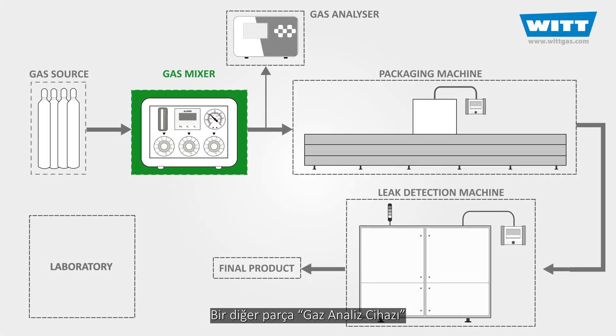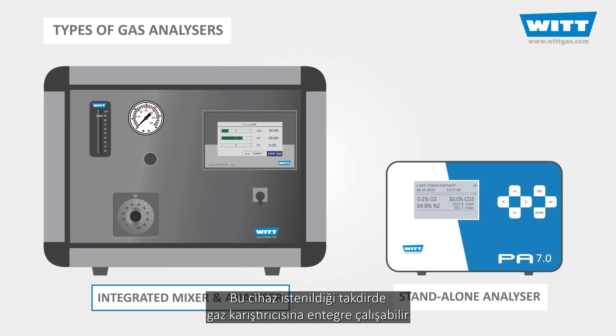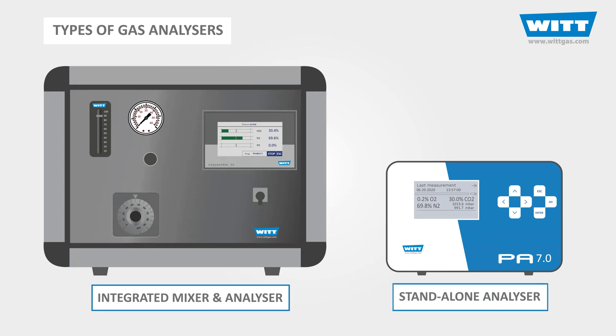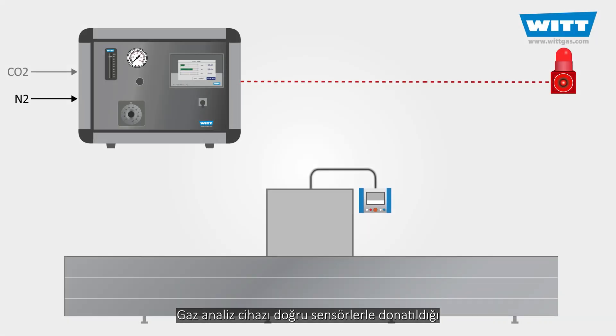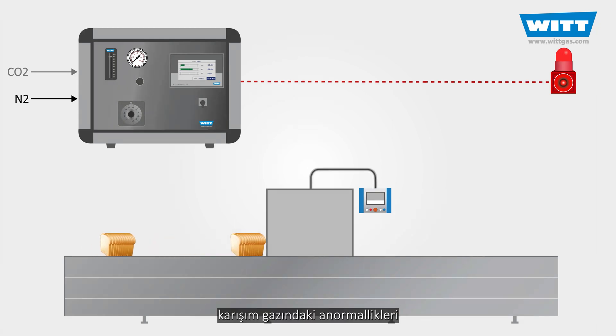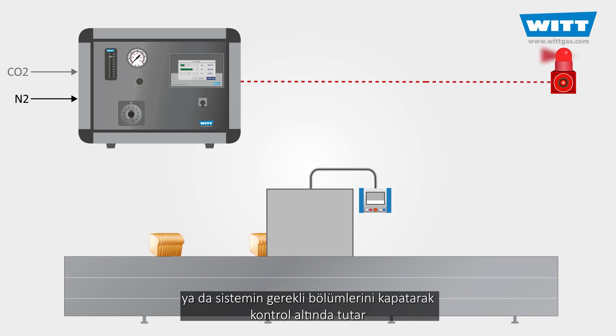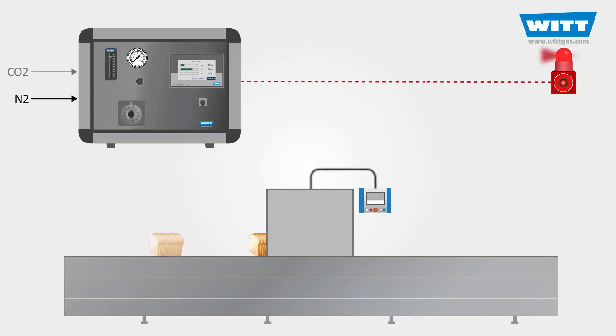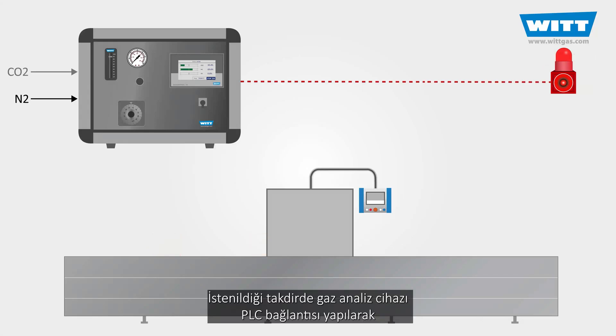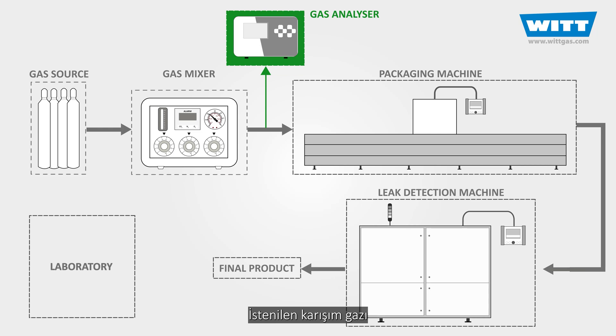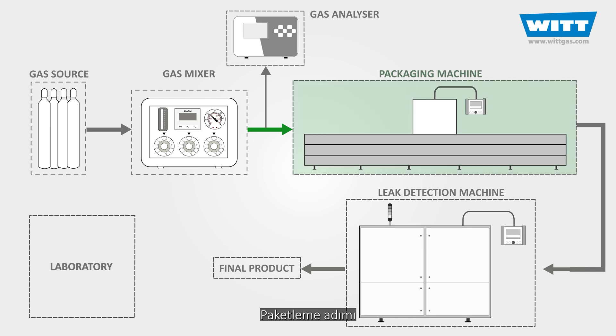The next component is the gas analyzer, which could be integrated into the gas mixer or could be a standalone unit for monitoring the exact real-time percentages of the gases. Equipped with measurement sensors, the analyzer will work in conjunction with the mixer, and in case of any anomalies in the gas mixture, it will inform the operator by activating an alarm, or will directly shut down the whole or a specific part of the system. The analyzer can be connected to a PLC as well, and be integrated into the main control system.